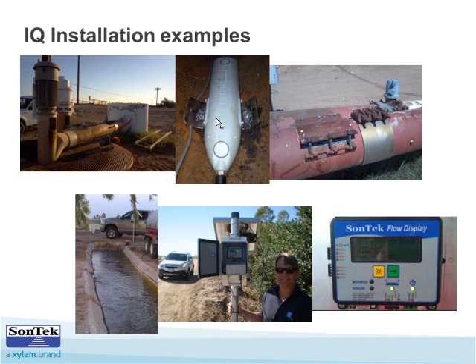Perhaps the person who wrote this question was well informed that if you have sedimentation in there, sometimes it's not a problem at all, but it becomes one after the instrument goes dry, and that sediment hardens and packs into the pressure sensor, which creates a problem. So the placement of these orifices is different. It's not just a port, it's a flow-through cell that minimizes sedimentation, and even the sides of the housing are aerodynamic so the flow shears off and minimizes settling into the orifices.